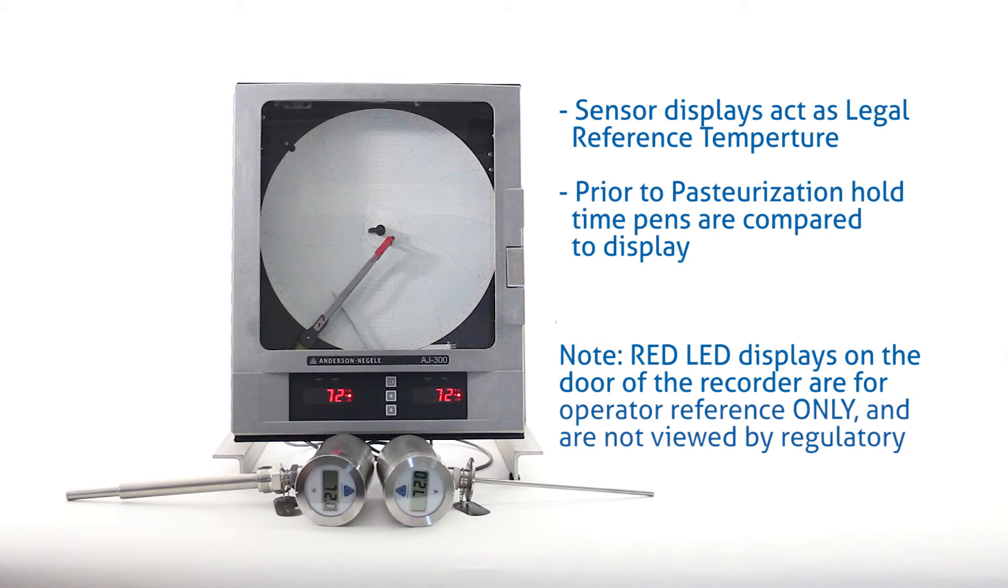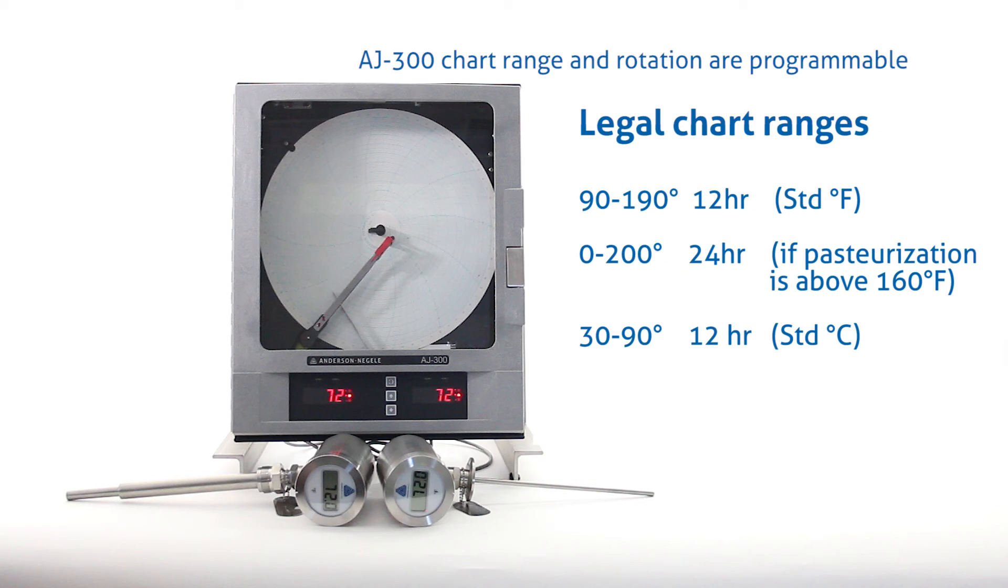Prior to the beginning of hold time for product pasteurization, the recording pens are compared to these displays. The red LED displays on the door of the recorder are for operator reference only and are not viewed by regulatory. The AJ300 chart range and rotation are programmable.